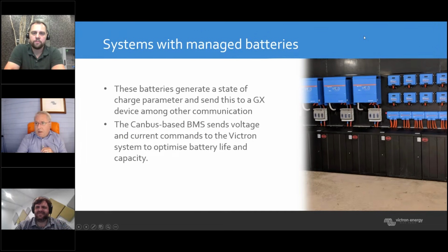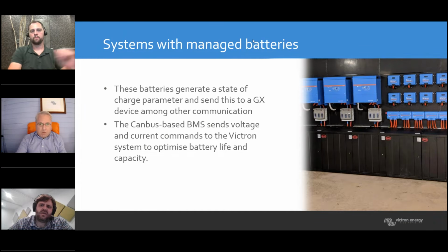There you go. So what he's referring to is that as part of the inverter chargers we have, we also have a line of modular DC bus bars which can be put together in systems for attaching batteries. We have fused options called the Lynx Distributor, and we also have ones that are just regular bus bars with posts directly on them, called Lynx Power In. Between these two and the shunts, well, we wouldn't need a shunt with a Fortress battery because it's a closed loop system. But for other battery systems, like AGMs and 2-volt cells, there is a shunt option that fits neatly within that form factor. So it's a good way to neaten up a system, make it very organized, and quickly see where there are any issues in the system on the DC wiring side.